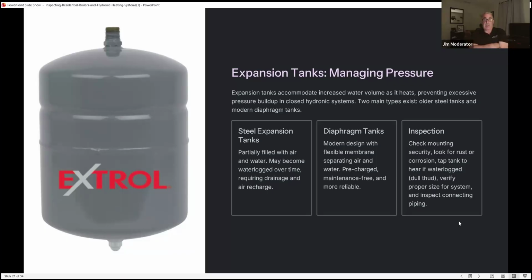So the steel tanks, I don't see a lot of them anymore. I do see them. The diaphragm tanks I see all the time. I do tap on them. As for the installation, I've seen them installed vertically and horizontally, and my heating guy tells me both are acceptable. I don't like the horizontal installation because I think that if they fail, that's going to put stress on the threads, but my guy keeps telling me I'm wrong. So I do mark it if it's horizontal, but a lot of times I'll see them horizontal with a piece of wood underneath in case it fills with water. That's not really going to do anything if it fails.